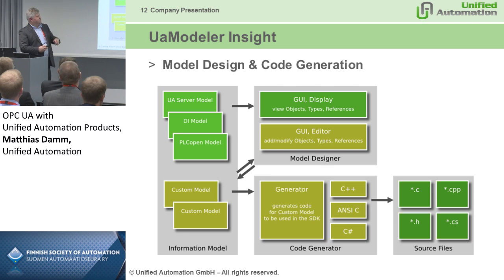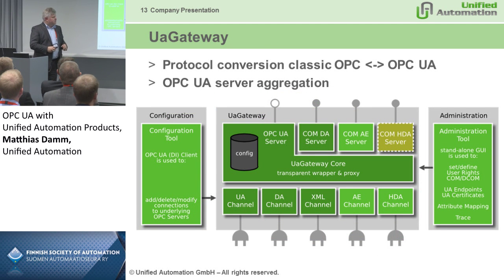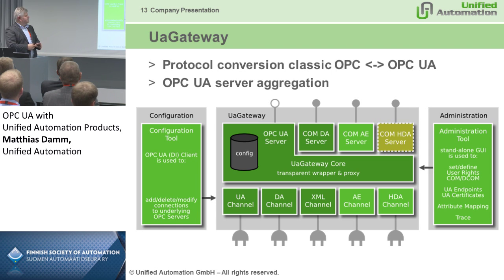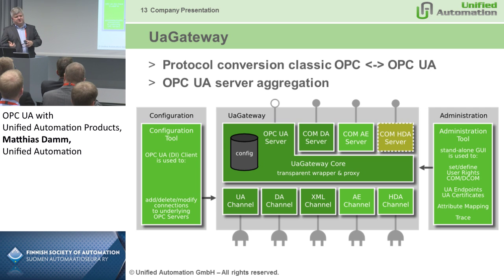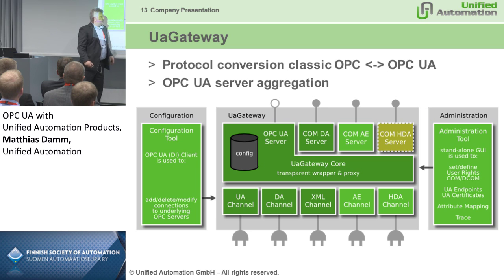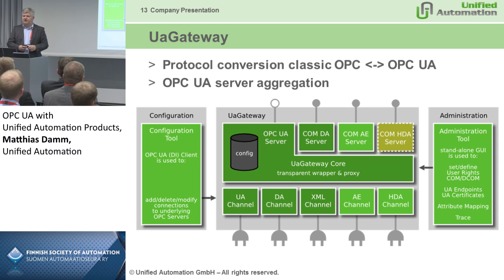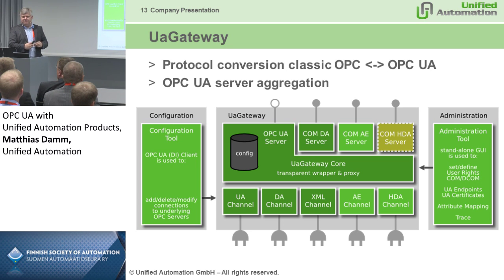The last tool is UA Gateway — it's a protocol converter. You can connect any OPC UA client to any classic OPC interface, or classic OPC clients to OPC UA. It has different OPC UA client interfaces and different OPC server interfaces. It also allows OPC UA aggregation — you can aggregate different OPC UA servers into one address space. It's not limited to data access; it has the full blown OPC UA functionality for the aggregation part.